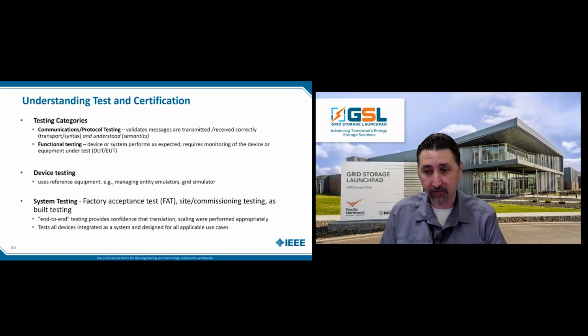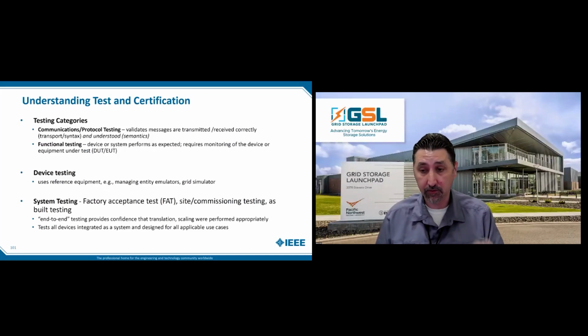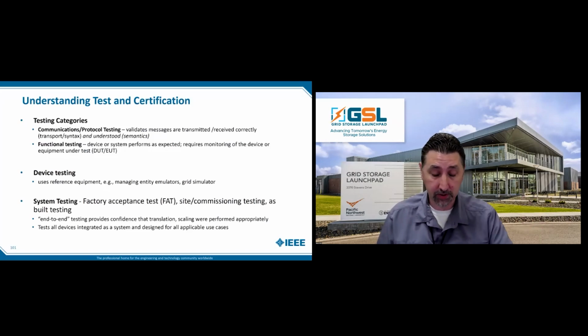Now we're getting into the fun stuff. In the testing and certification component, we have different categories of testing. You have communications protocol testing, the bits on the wire, and then functional testing - meaning if something was told it needed to ramp up or down, or needed more real or reactive power, did it actually do what it said? Then you have system testing, usually done on site - factory acceptance testing, as-built testing - which just means all the components worked together as they were supposed to.